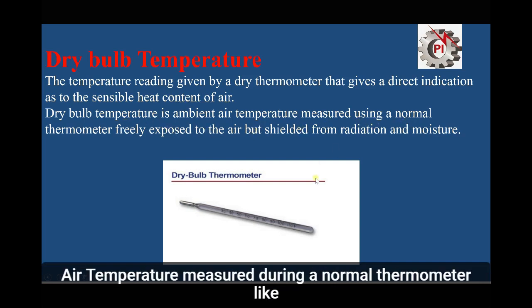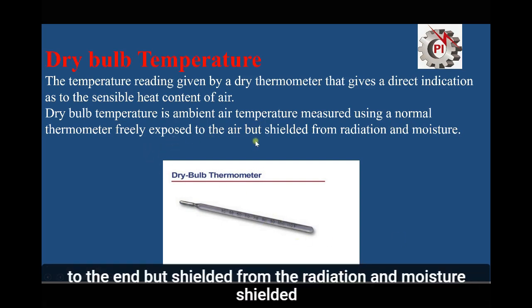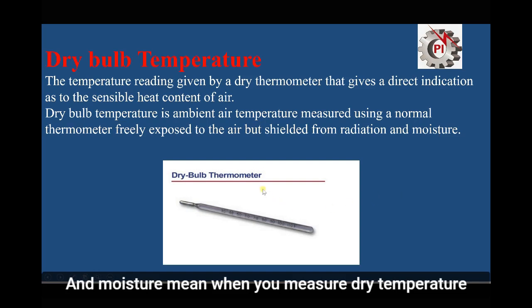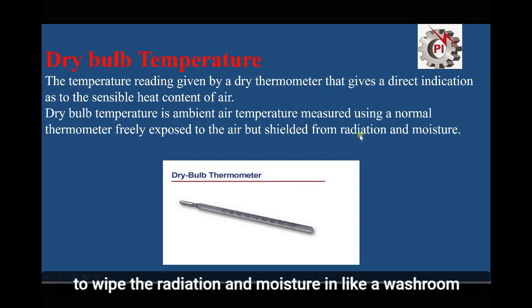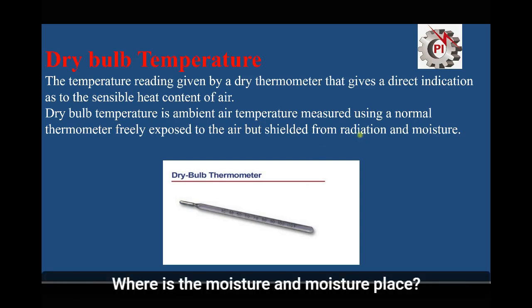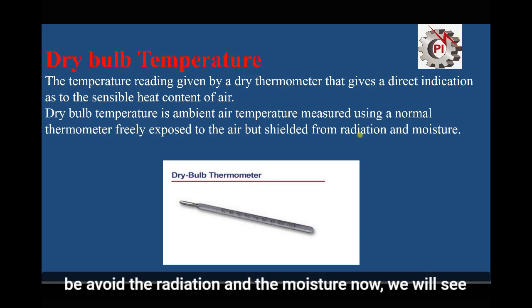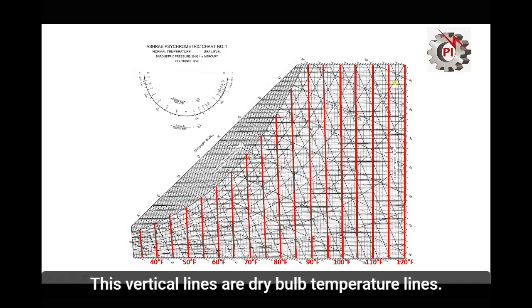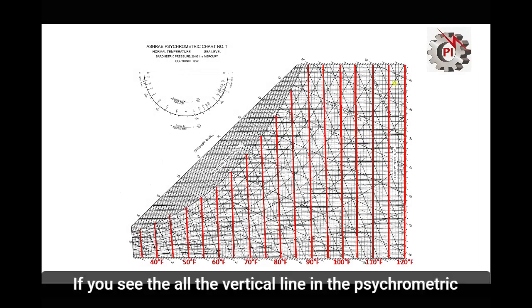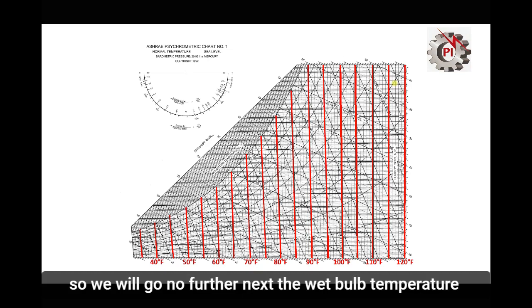Dry bulb temperature is the ambient air temperature measured by a normal thermometer freely exposed to the air but shielded from radiation and moisture. When measuring dry bulb temperature, your thermometer should not be near a fireplace to avoid radiation, and not in a high-moisture place like a washroom. In the psychrometric chart, the vertical lines are the dry bulb temperature lines.